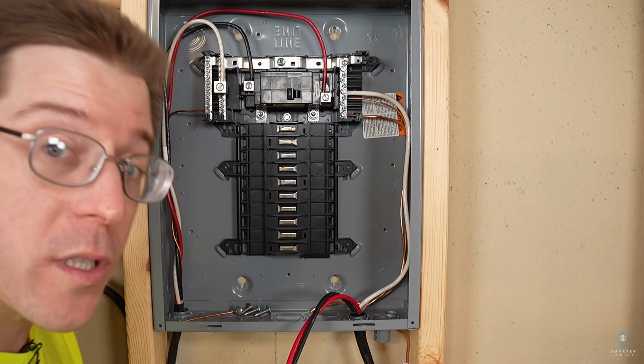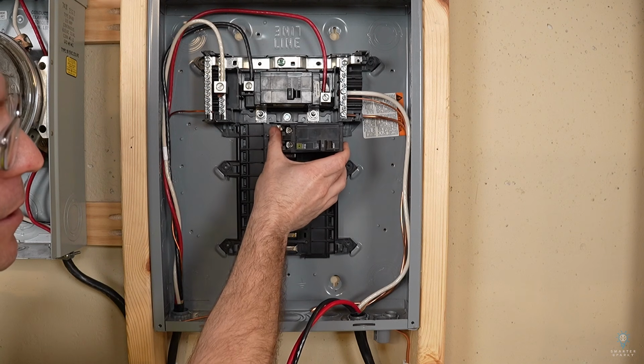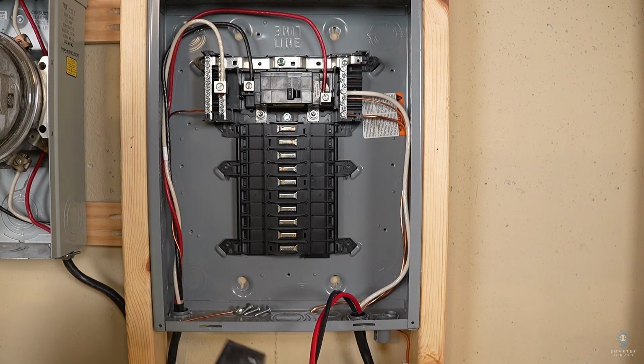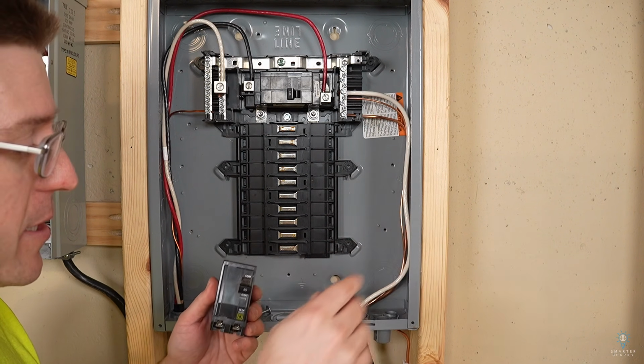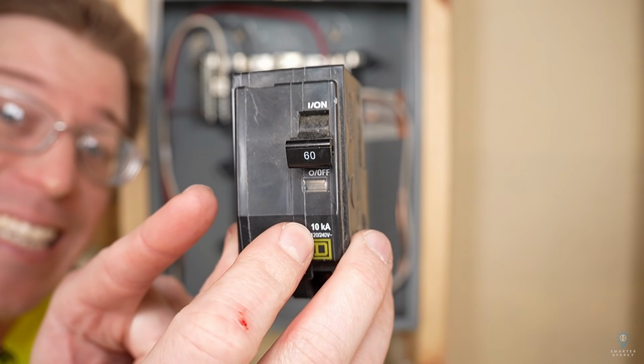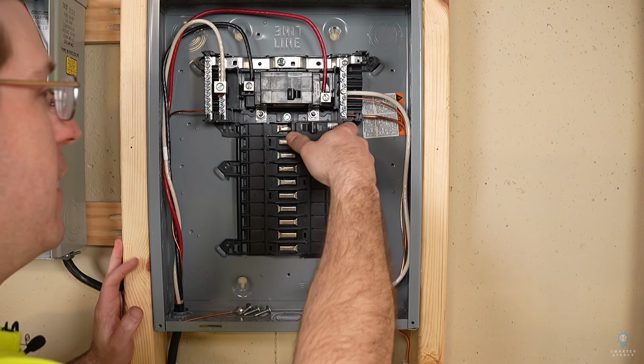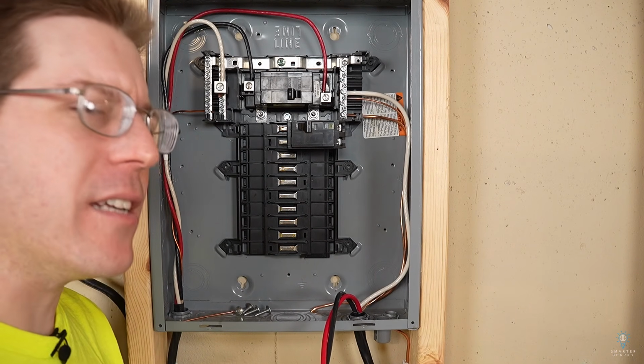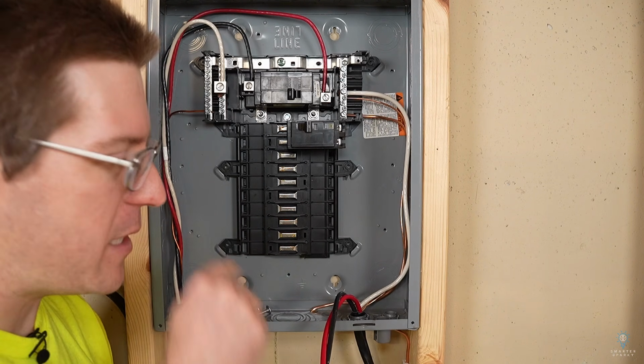Where do we land those? For those, we need to install a circuit breaker in the panel. So in this case, because we're installing a 60 amp sub panel, we are gonna be installing a 60 amp breaker in the main panel. This breaker simply snaps in and then snaps into the bus bar. Again, check out that main panel video for a little bit more detail on that step.